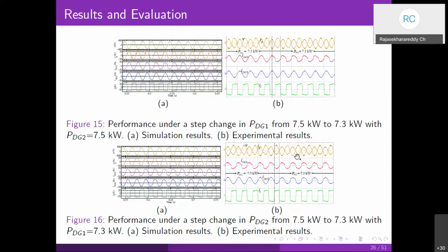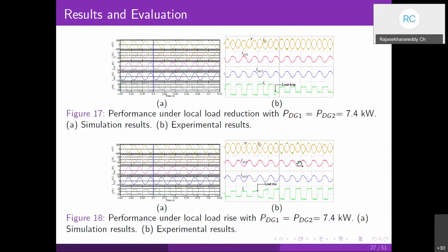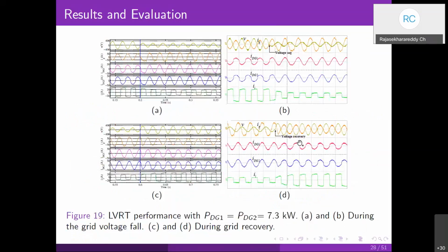You can see here both the currents are not sinusoidal because they are offering harmonic currents compensation. An improvement in grid current can also be seen when we have fully compensated these harmonic and reactive currents. Similarly, you can understand the effect of load change. Initially, when we connect full load, that means the load is at rated value, both the DGs are partially providing the compensation of harmonic currents. When the load is reduced, they are fully able to compensate the harmonic and reactive currents of the reduced load. That is the same as the previous case.